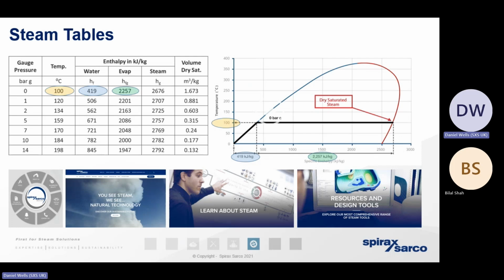Now, the problem we have with the steam tables is, academically, they're a fantastic resource. In the real world, the problem with the steam tables is they assume that the steam that is being produced on our client site is 100% dry 100% of the time. And it never is. So if we move across to the graph at this side of the screen, this is what we call the temperature enthalpy curve. And it plots the journey that that kilogram of water takes when it boils off, when it changes state from a liquid to give us steam as a gas.